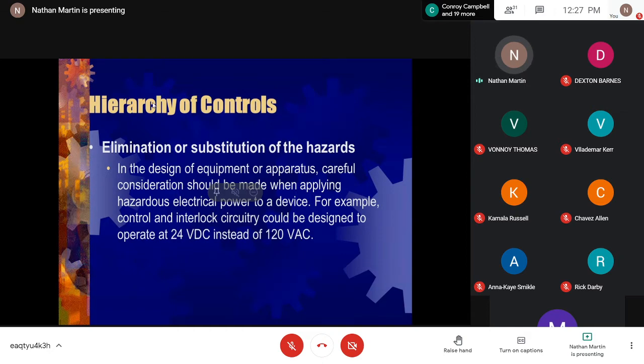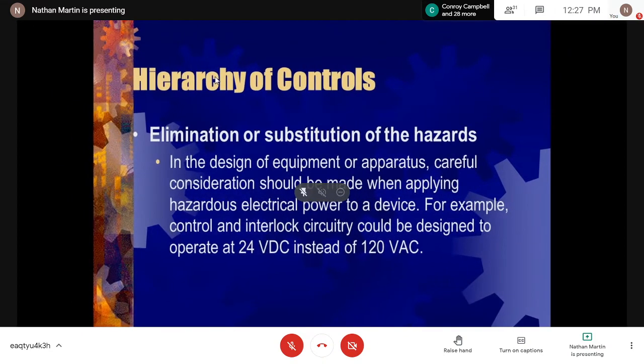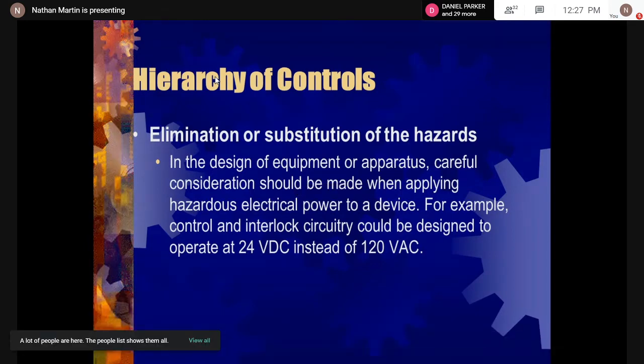When talking about electrical interlock, we're talking about low voltage values such as 24 volts DC, instead of 120 volts. Even though we can get shock from DC, we're talking about high voltage DC in those cases. So a 24 volt DC interlock circuitry will not pose as much danger to you as the operator.